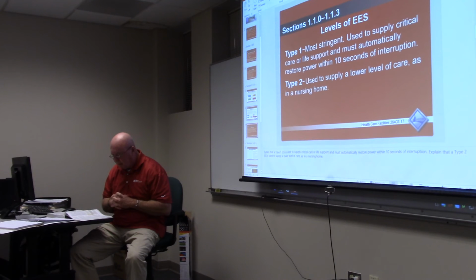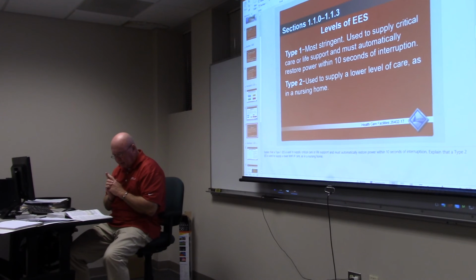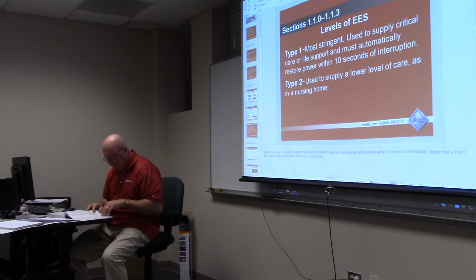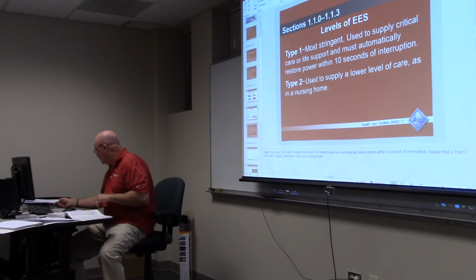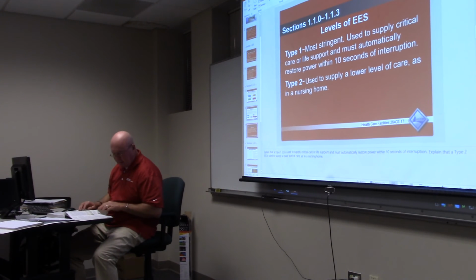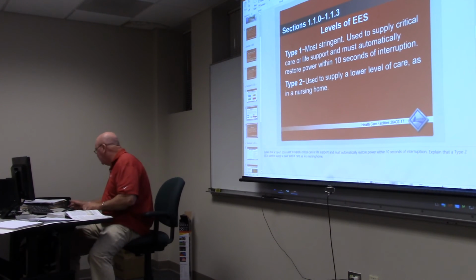The critical branch of the type 1 EES may consist of one or more branches designed to serve a limited number of receptacles in a location to reduce the load demand. In other words, it gets specific as far as the circuitry is concerned, as we were talking about earlier. Let's take the code book for a second and see what 517.18a actually says.